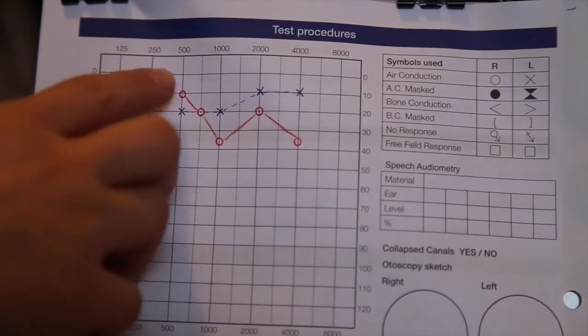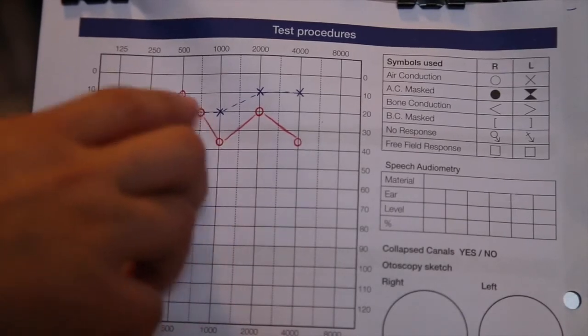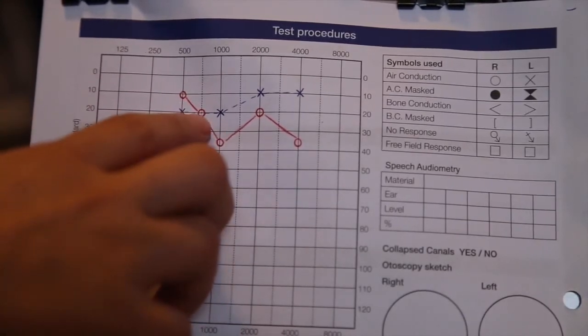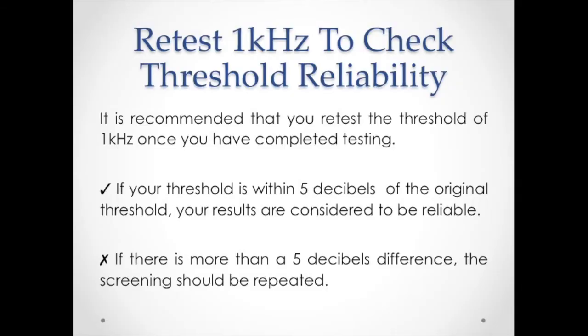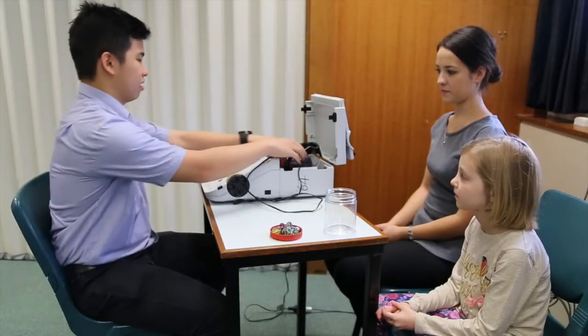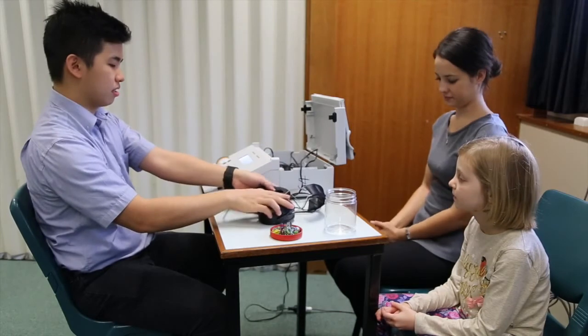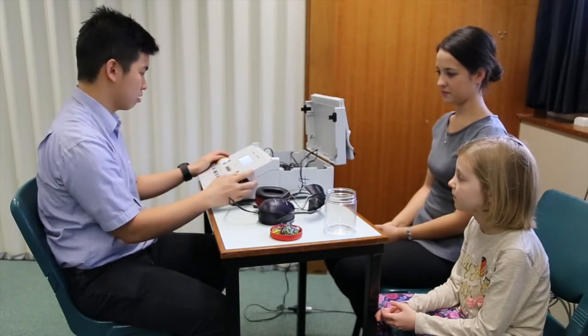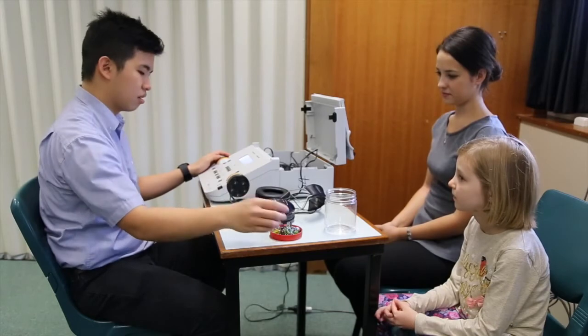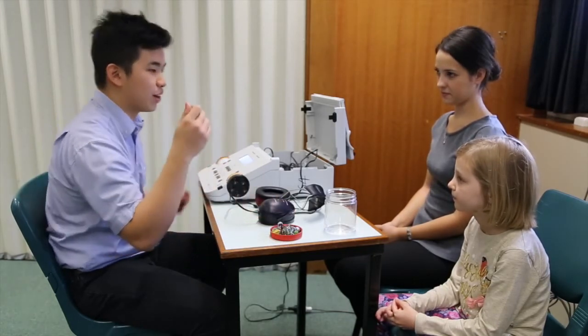If there's a difference between the consecutive frequencies of more than 20 decibels, you may wish to test the intermediate frequency. It is recommended that you retest the threshold of 1 kHz once you've completed testing. If your threshold is within 5 decibels of the original threshold, your results are considered to be reliable. If there's more than 5 decibels difference, the screening should be repeated. The type of assessment you carry out for a screening should be age appropriate. Play audiometry is suitable for children over 2.5 years. Pure tone audiometry tends to be suitable for clients 5 years and over.